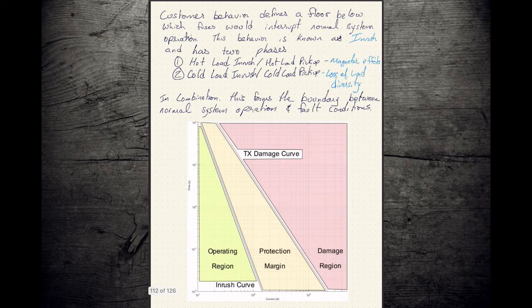And then the other thing we looked at was our inrush behavior, and a couple of different things play into that. There's that initial very short period of time when you're just powering things up, and our transformer cores, which have that magnetic tank we talked about, which provides a back EMF or a back pressure, which is why a transformer doesn't behave like a short circuit, even though if you look at them from a static perspective, they look awful similar. So while you're setting up that magnetic tank and filling it up and getting that back EMF established, you get some very high current flows.